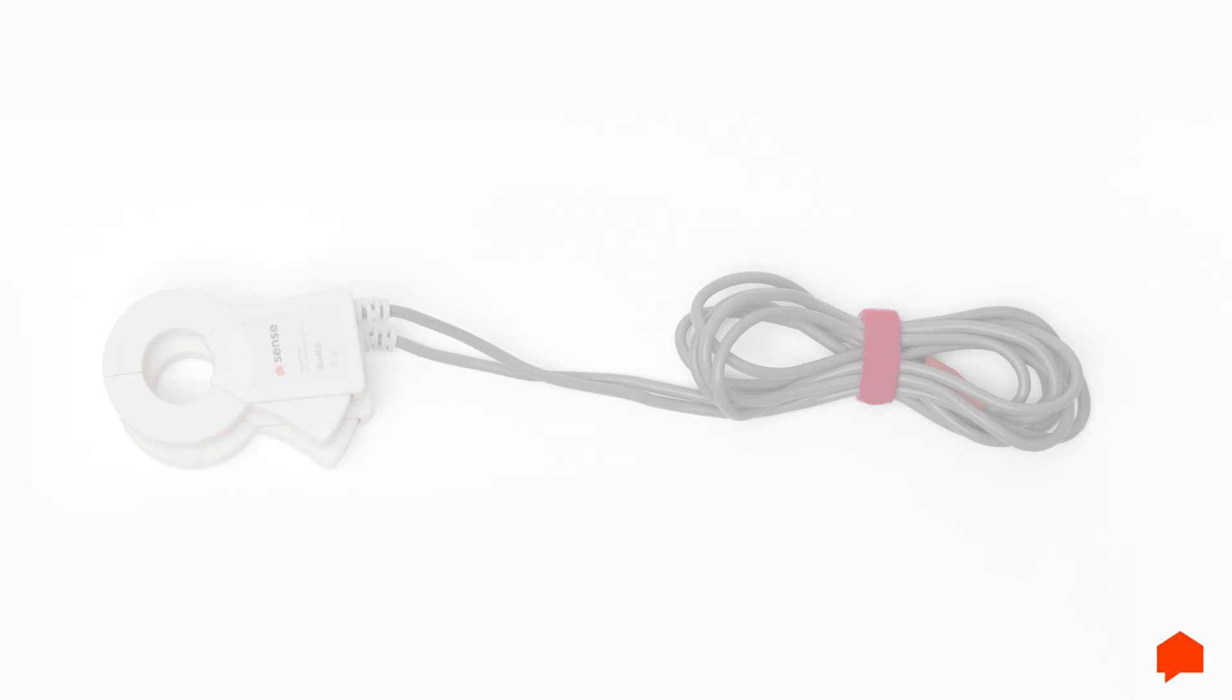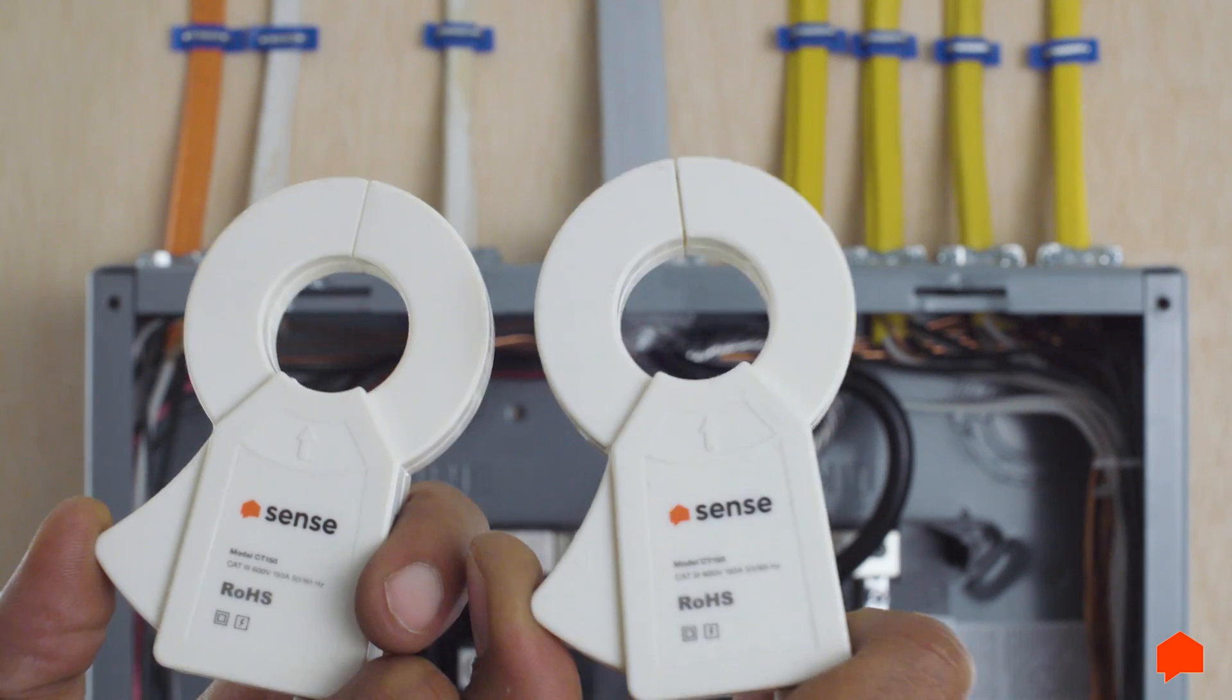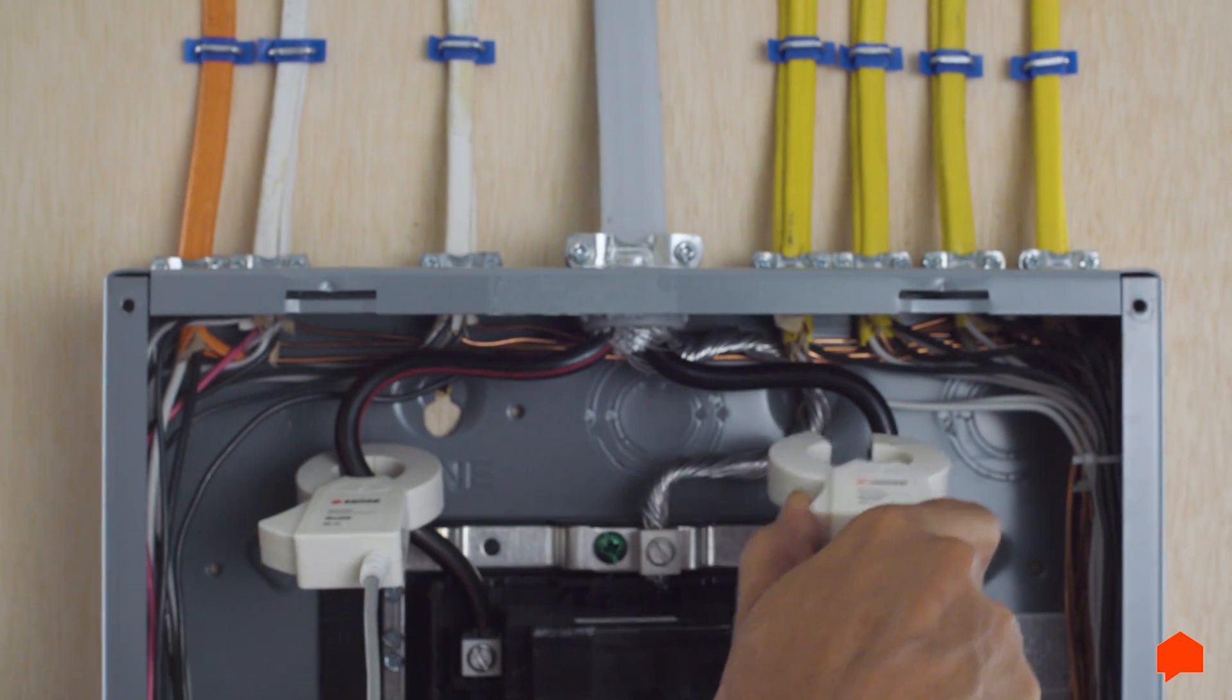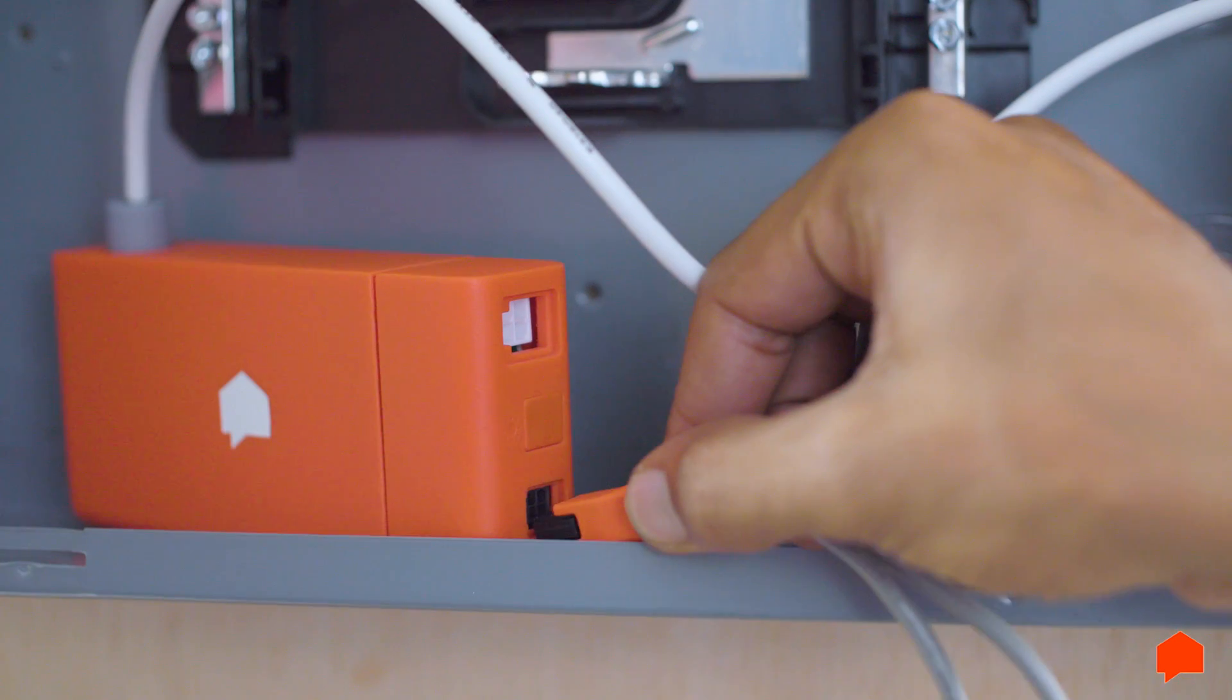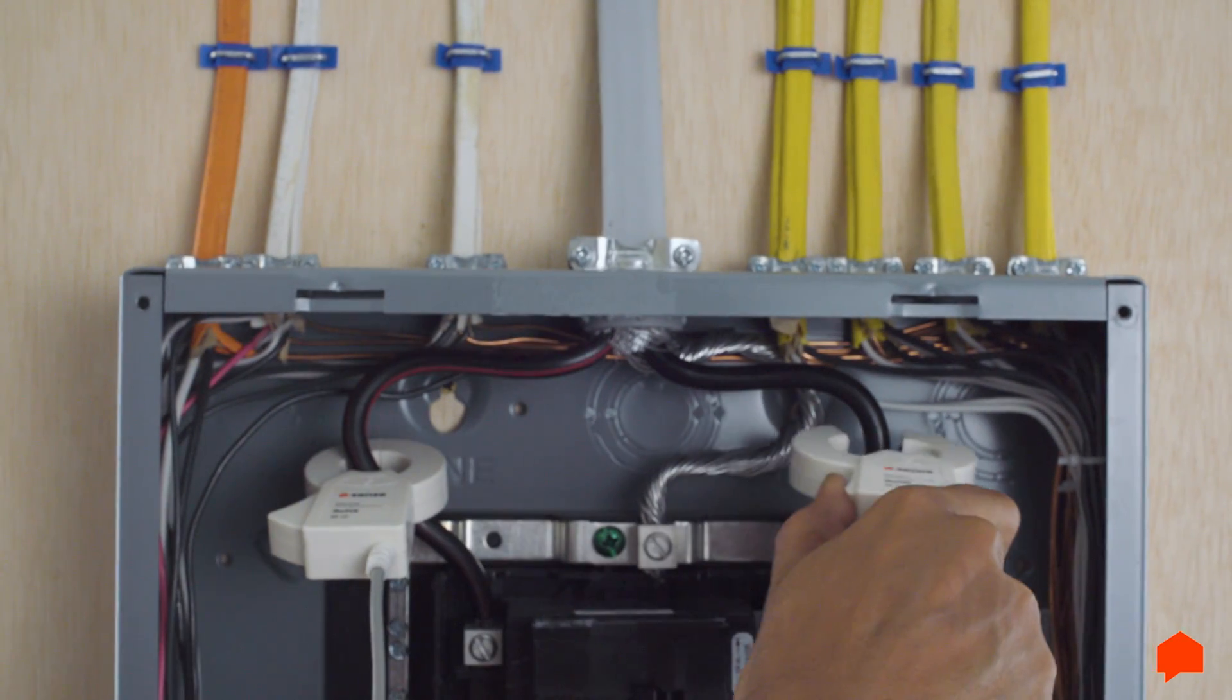On to the sensors. Make sure that the labels on the two current sensors are both facing the power source. If your service mains have loops, follow the loops to make sure they're facing the same direction. Clamp the current sensors around the two main service breakers. For safety reasons, it's important that you first plug the sensor cables into the monitor and then attach them around the mains.